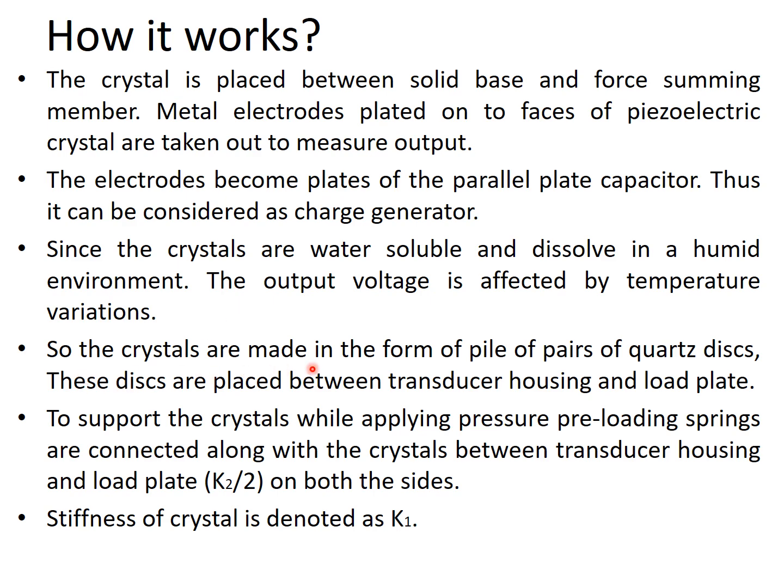Since this transducer comes under the active transducers, the crystals are made in the form of a pile of pairs of quartz discs. These discs are placed between the transducer housing and the load plate. To support the crystals while applying pressure, preloading springs are connected along with the crystals between the transducer housing and the load plate on both sides.